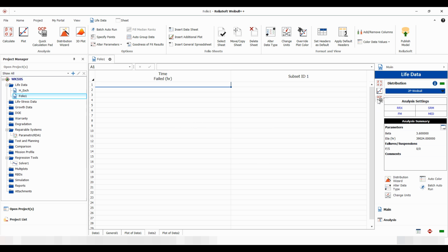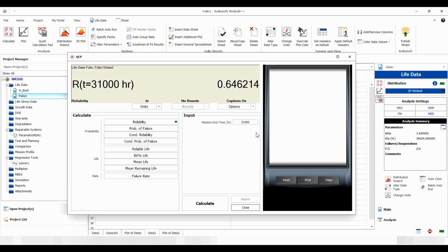So we fitted this model, and now we want to find the mean life. So we go to the mean life, calculate, and we have 35,164 against the, say, 35,000 from the OREDA. So we feel that with this approach, it could be a simple way of incorporating the OREDA data into a model that takes into account possible wear out.